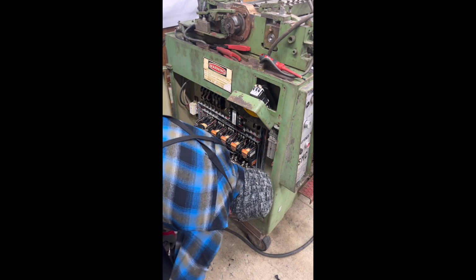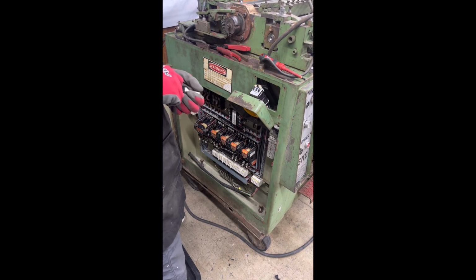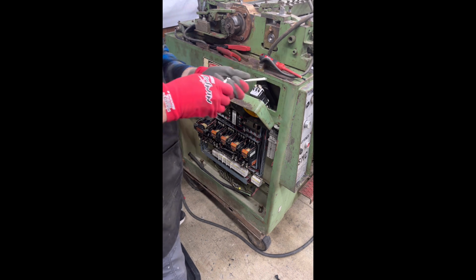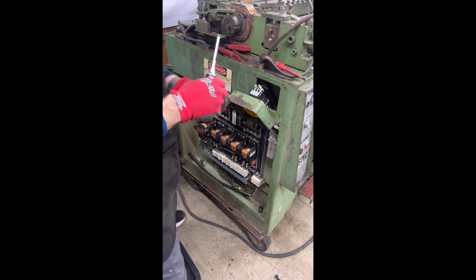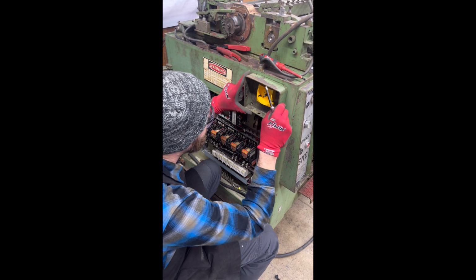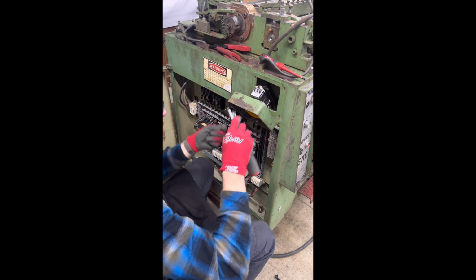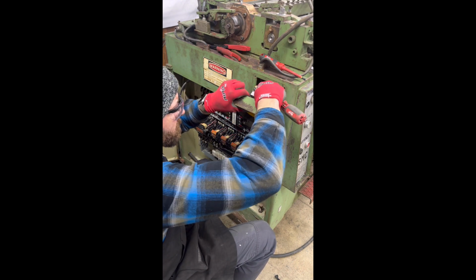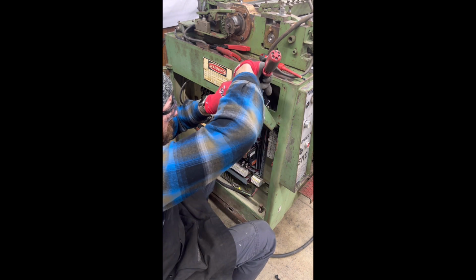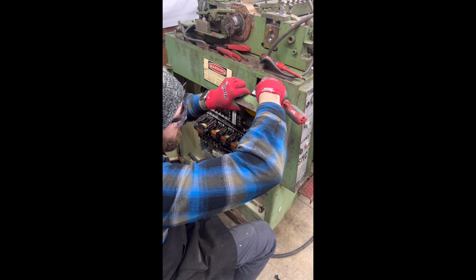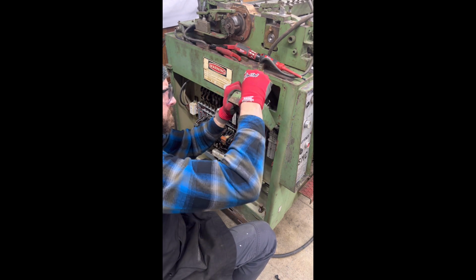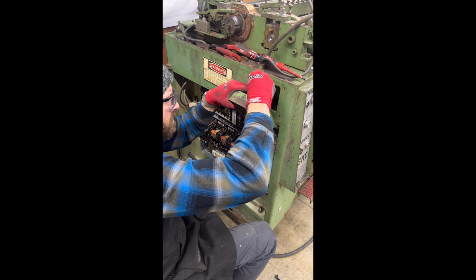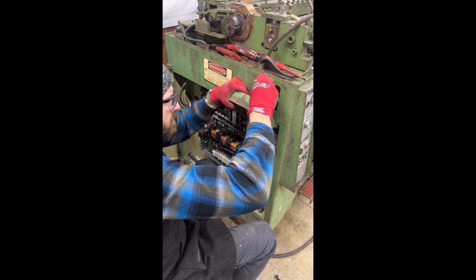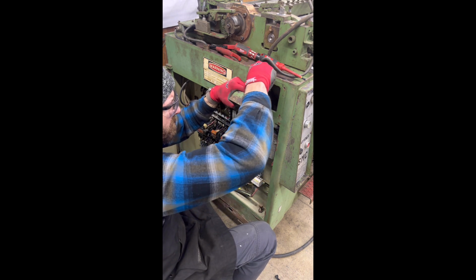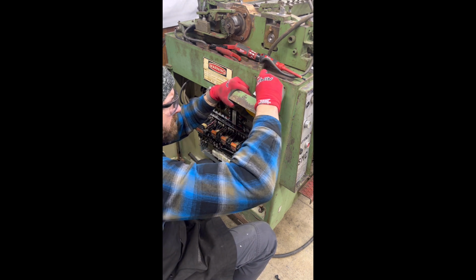Here I'm getting the disconnect installed. However, off camera, I actually end up pulling the plate back out and re-drilling the holes with the disconnect switch centered at the very bottom of the factory hole. I didn't like how close the top of the disconnect and the wires were to the chassis. I was afraid that the wires would end up eventually chafing and wearing through with the hard bend they needed to clear the top.